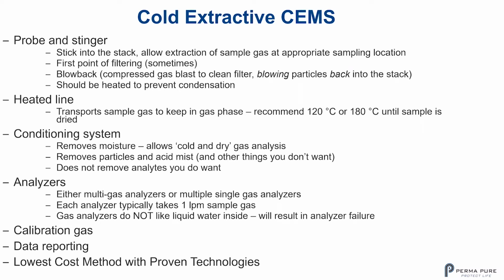And this stinger and probe should be heated to prevent condensation. Typically, the dew points of the gases coming out of the stack can be as high as 70 degrees C. And you need to keep the probe and the whole sampling line way above that dew point in order to prevent condensation. You also then have the heated line, which transports the sample gas to keep it in the gas phase.